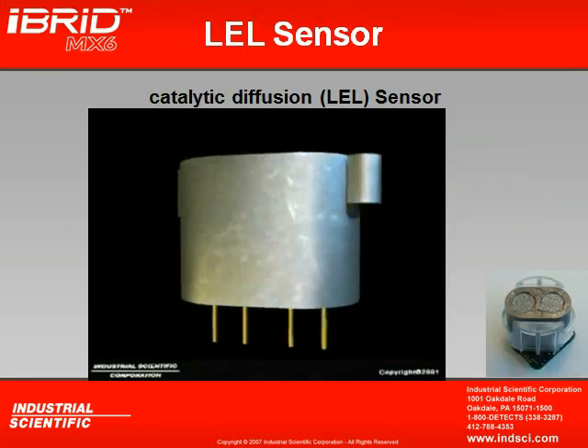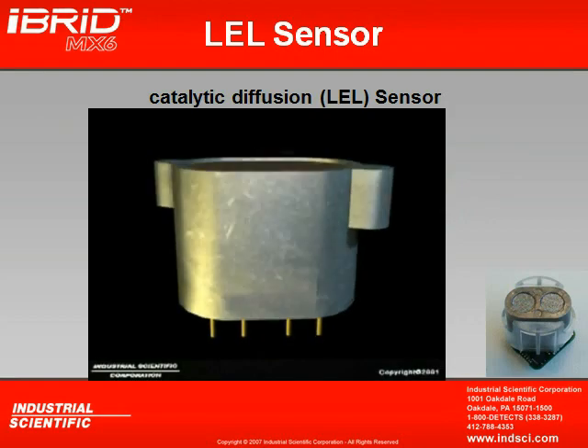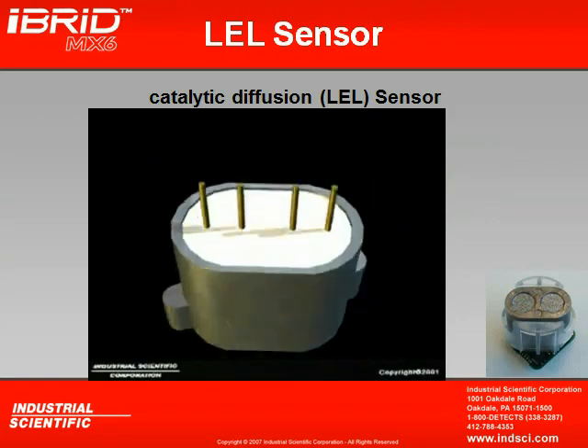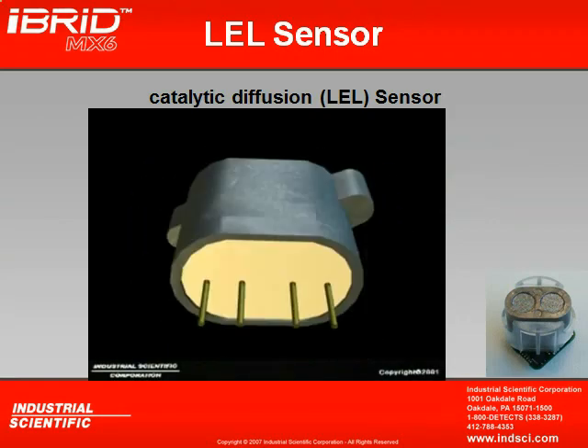So let's go ahead and look at the catalytic diffusion sensor. Some people call it an LEL sensor. Some people call it the combustible sensor. Regardless of the name you give it, this is a sensor that detects combustible gas. It detects any and all combustible gases because of its principle of operation on the inside.